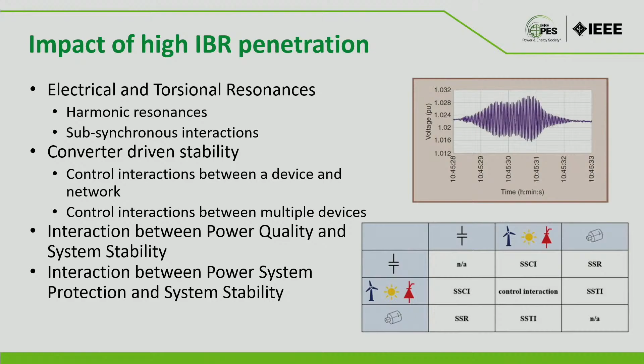On the bottom right, it's summarizing what could happen. If you've got an IBR and it can interact with another IBR - could be a wind farm, solar farm, or an HVDC system - it could create a control interaction. If there are IBRs interacting with rotating machinery, it could create a subsynchronous torsional oscillation. You might have this frequency of oscillation in the grid which could coincide with the natural resonance of rotating machinery, causing a subsynchronous torsional interaction. When the shaft has a number of masses, it can interact and damage the shaft.